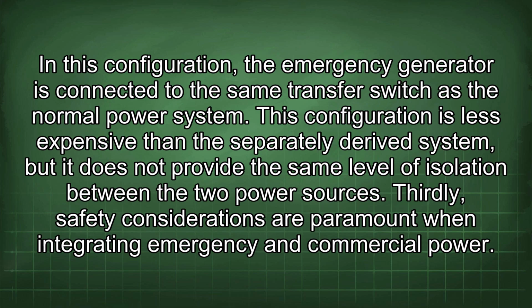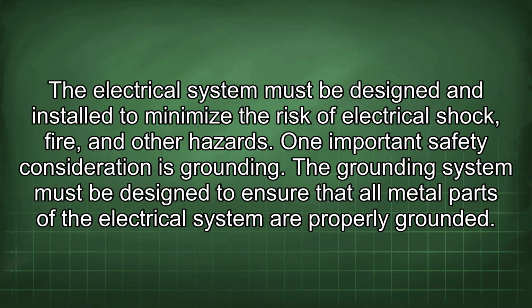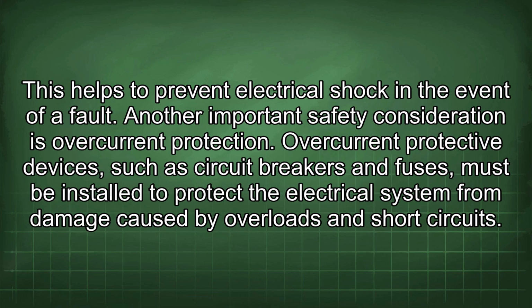Thirdly, safety considerations are paramount when integrating emergency and commercial power. The electrical system must be designed and installed to minimize the risk of electrical shock, fire, and other hazards. One important safety consideration is grounding. The grounding system must be designed to ensure that all metal parts of the electrical system are properly grounded. This helps to prevent electrical shock in the event of a fault.